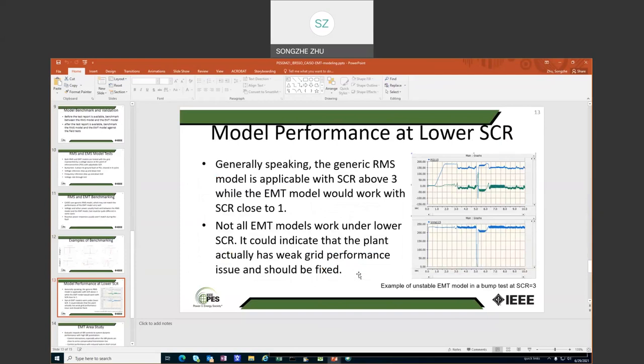So generally speaking, the generic RMS model is applicable when SCR is above 3, and it may still work well for SCR between 2 and 3. But usually the RMS model should not be used to evaluate performance if SCR is below 2, while the EMT model is expected to work with SCR very close to 1. But that's not always the case. We have seen that some EMT models don't work at SCR equal to 3. So it could be just a model problem. The model isn't accurate.